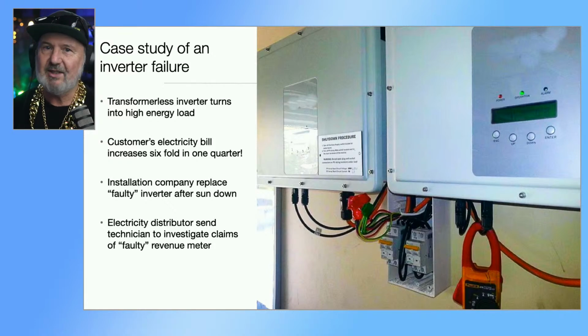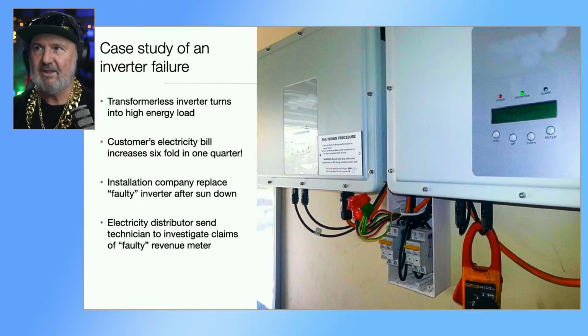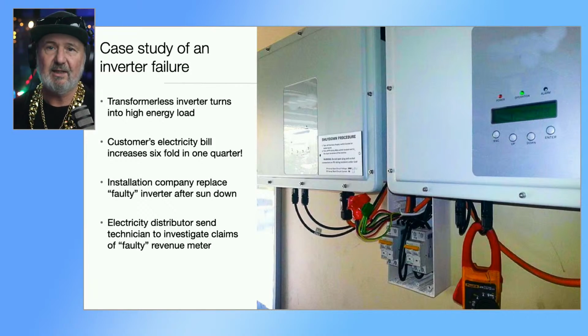So coming back to the case study here, this was a transformerless, or actually two transformerless inverters. That means there's no galvanic separation between the AC and DC side, which is basically every inverter these days. Every solar inverter is transformerless, mainly because of efficiency, cost and weight. So we've moved away from galvanic isolated transformer-based solar inverters.